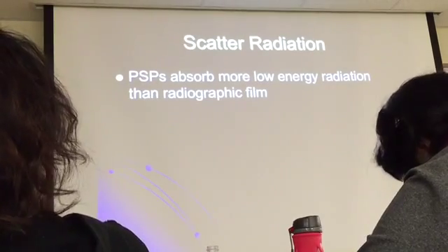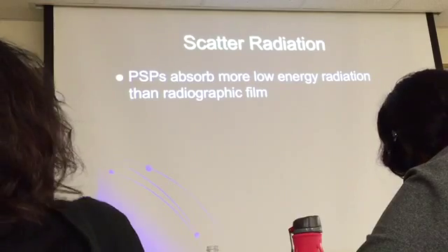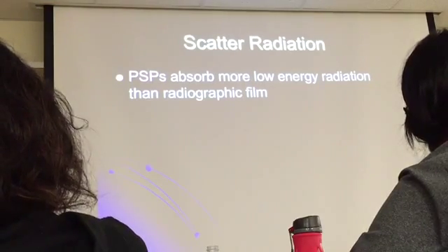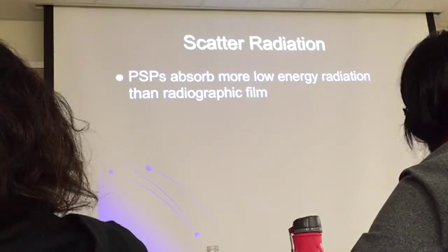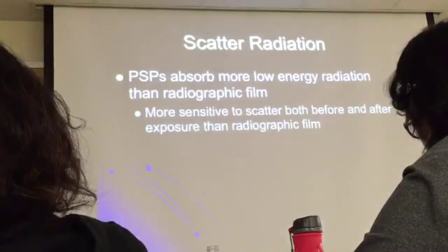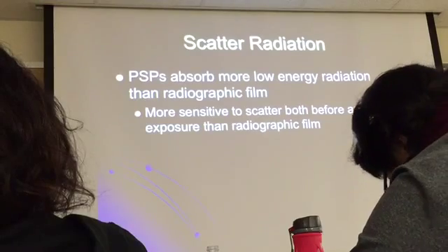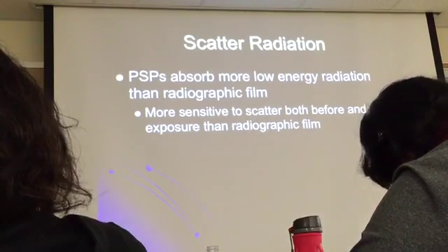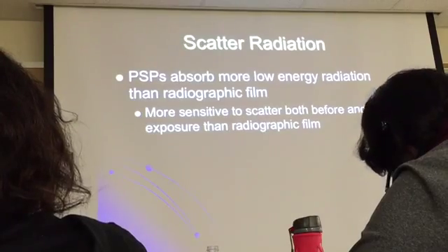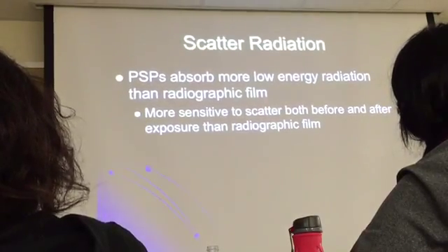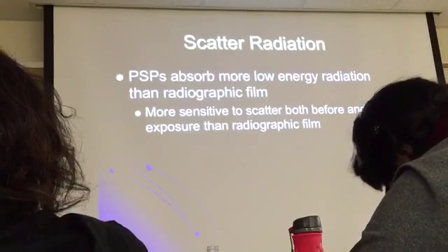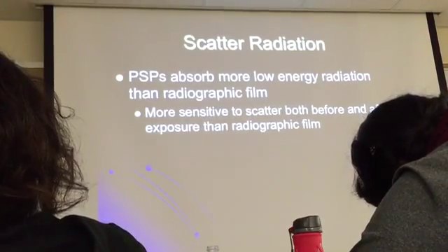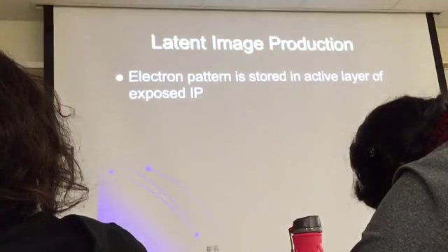They are more sensitive to scatter both before and after the exposure compared to radiographic film. With radiographic film, there were times where you did a portable and left it in the radiographic room, and it was fine if you had enough distance. But this is very sensitive, so you need to be careful.